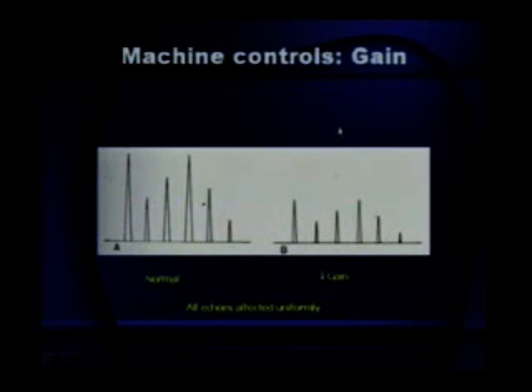Gain is the control which we use very frequently. What gain does is that it uniformly reduces or increases the amplitude of all the echoes that we are receiving. For example, these are the echoes that are being received, and on this axis is the amplitude or intensity of the echo. So if we reduce gain, all the echo signals get affected equally. Intensity of all is reduced. So that is how the gain function works.